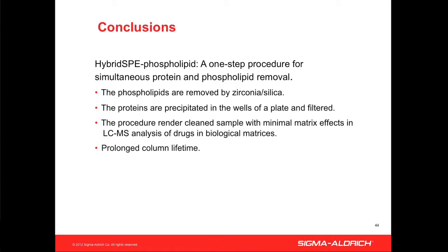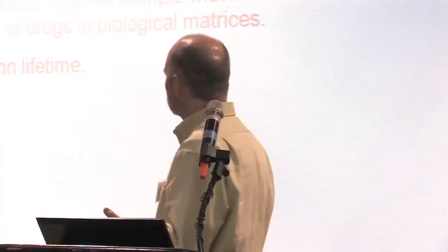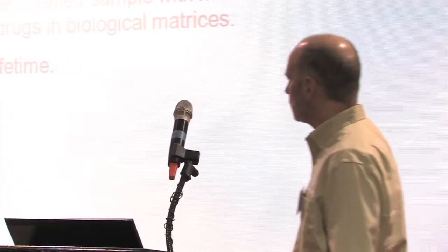And one of the real advantages that we haven't mentioned here at all is really prolonged column life. We've done these sorts of studies looking at back pressure and buildup of phospholipids, and instead of a typical case where you often are running gradients to clean up columns, not only is that gradient removal actually ineffective over time, you might think it looks effective if you're just doing it once, but over time phospholipids are in fact accumulating. But if you do this pre-treatment with applying this hybrid SPE, as I showed you here, the amount of phospholipids on the column is drastically reduced, and you don't need to do this sort of gradient cleanup nearly as often.